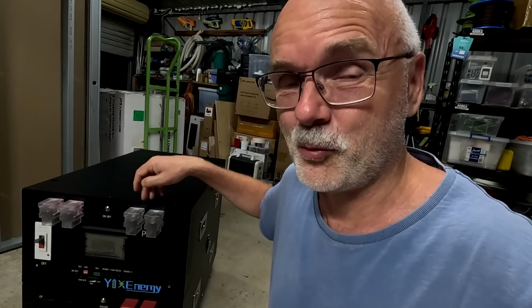I know this is an extreme case, so the circuit breaker will trip at 250, roughly. This is a safety device. So if your BMS, for whatever reason, does not trip at 200 amps, the circuit breaker needs to prevent the unthinkable. It can actually occur that you have 250 amps through your faulty BMS and through these thin wires of 20 and 25 millimeter.